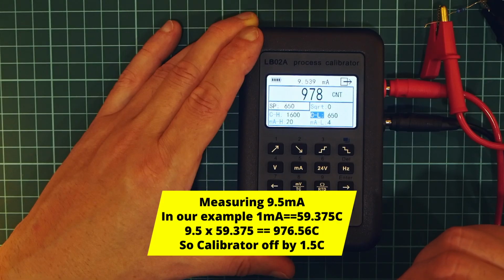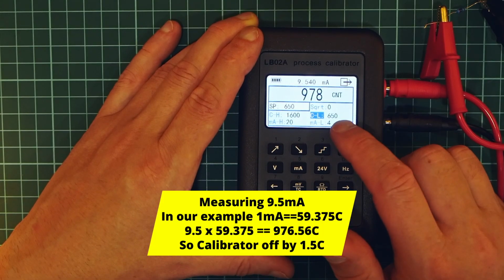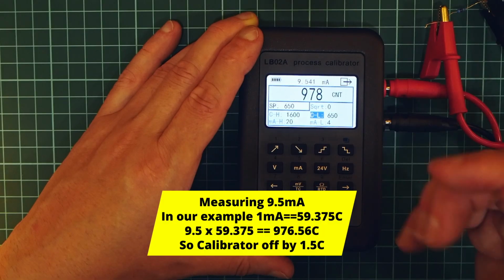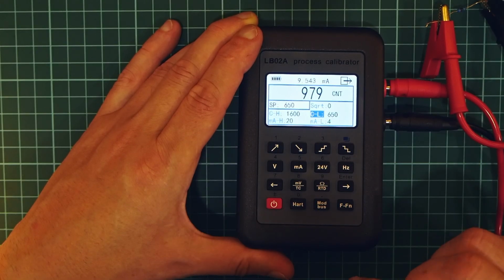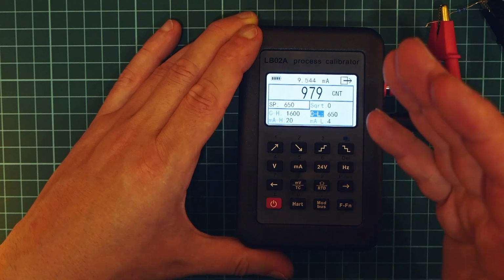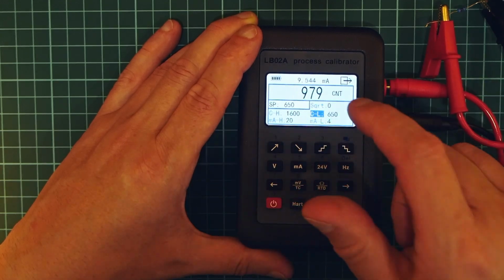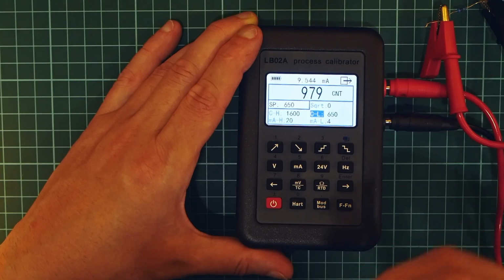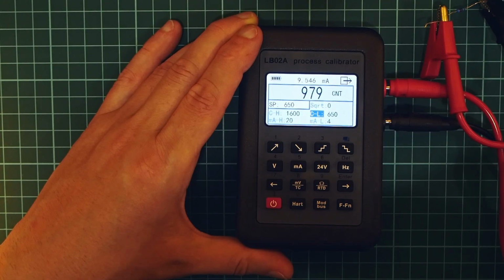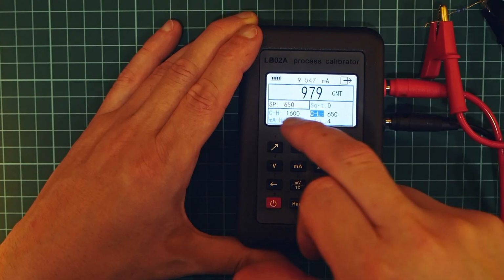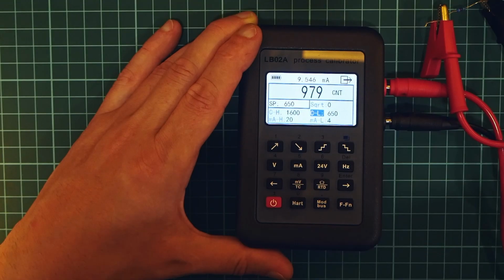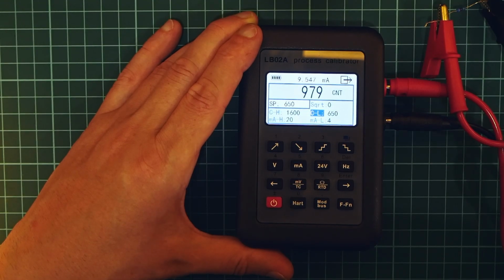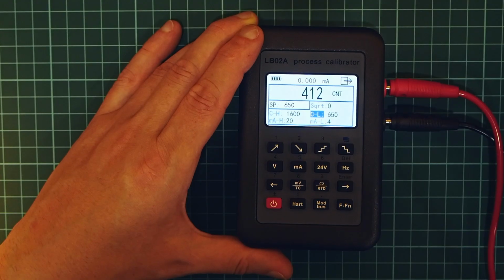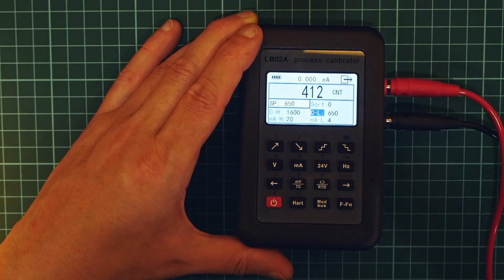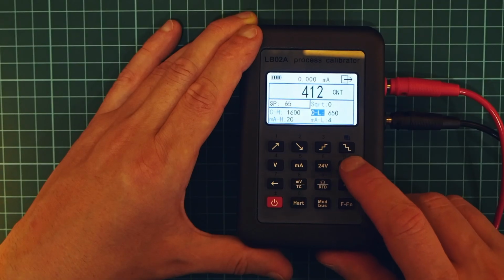So if you have a big low level in hundreds and big high level also in hundreds or in thousands, this counting will work fine. But if you are measuring from 0 to 20 bars, let's say, well, you could actually enter from 0 to 200, so you will have a little bit better resolution here, yes. This works fine. Don't have actual device to test this, but this works.